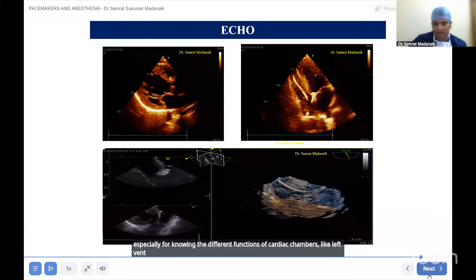Now, once you are done with the preoperative part, there are some intraoperative checks you should never forget before going further. So always remember, intraoperatively before induction, continuous ECG monitoring is essential. Pulse oximetry is essential. Invasive BP, if the patient is pacemaker dependent, you have to do. And remember, the ECG filter has to be set to diagnostic mode to visualize the pacing spike. If you set it to monitoring mode, pacing spikes won't be available. In patients with ICDs or CRTs, always remember to attach external pacing and defibrillator pads, and there are different positions for this.